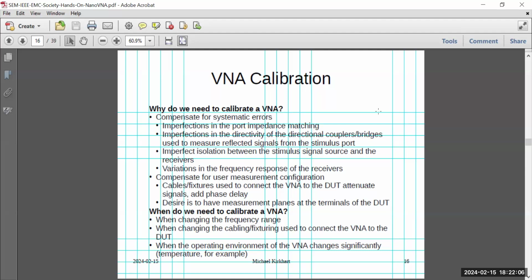So then, here's when do we need to calibrate it? When you power it up, whenever you change frequency range, you should recal it. When you change any of the cabling or fixturing, you need to recal it to reestablish that measurement plane right at your DUT. Another possibility is if the operating environment changes - you're in a warm room and it's getting warmer. I know it's a temperature controlled oscillator, but that just means it's somewhat compensated for that, not perfect. So if you start looking and things look a little weird, maybe you need to at least check your cal.